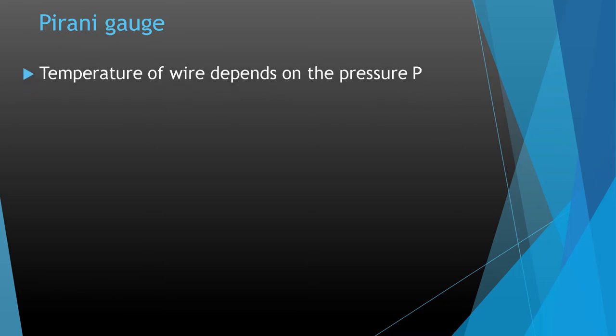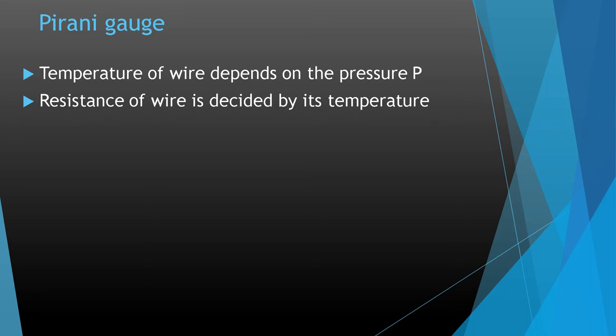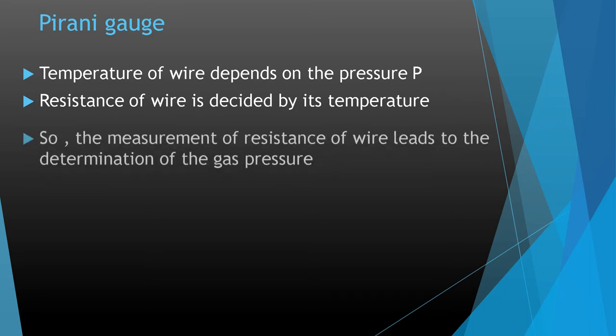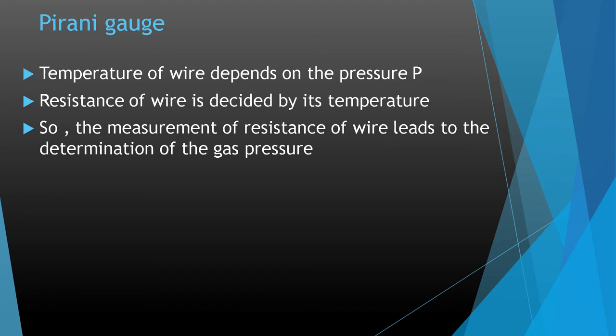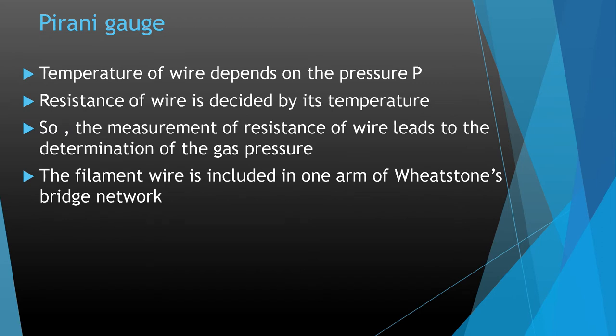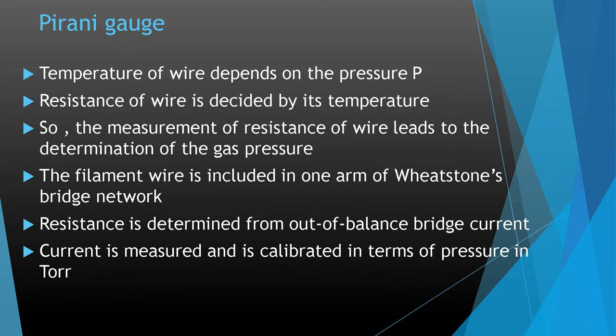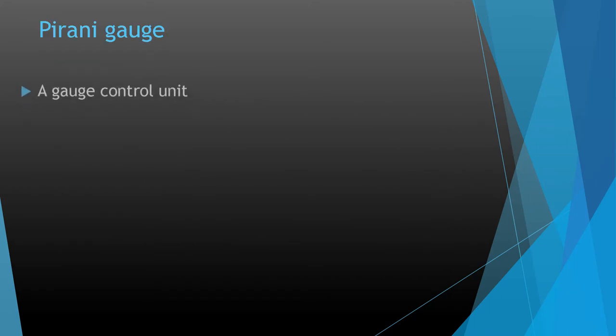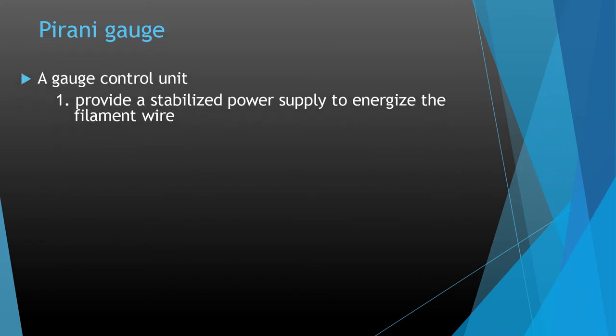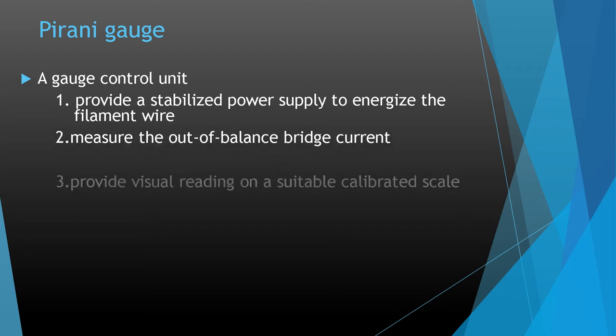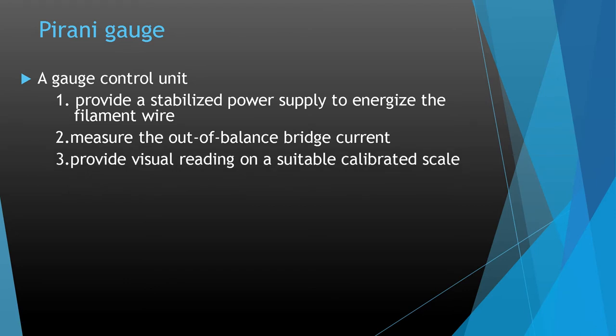In the Pirani gauge, the temperature of the wire depends on the pressure. The resistance of the wire is determined by its temperature, so measurement of the wire's resistance leads to determination of the gas pressure. The filament wire is included in one arm of a Wheatstone bridge network, and the resistance is determined from the out-of-balance bridge current. This current is measured and calibrated in terms of pressure in Torr. A gauge control unit provides a stabilized power supply to energize the filament wire, measures the out-of-balance bridge current, and provides a visual reading on a calibrated scale.